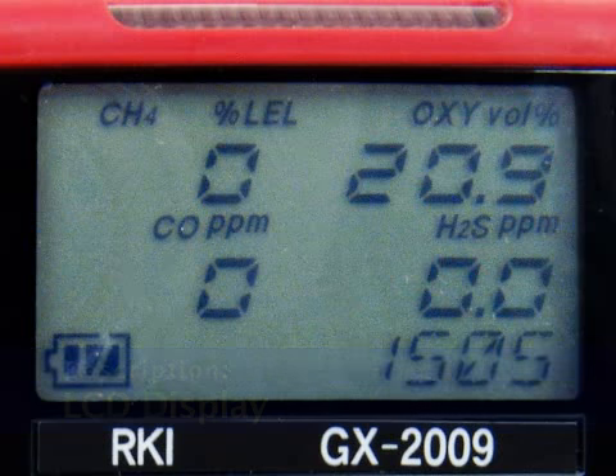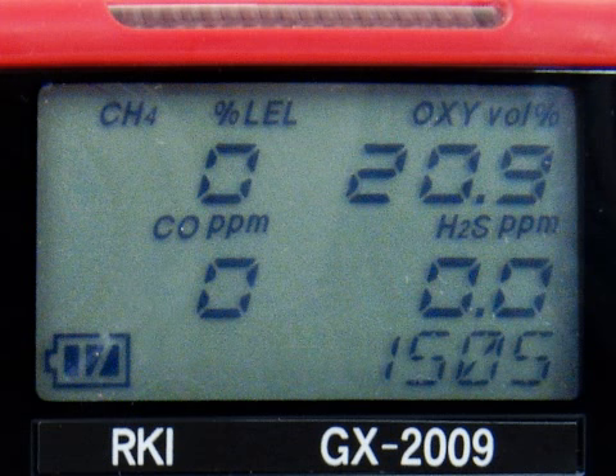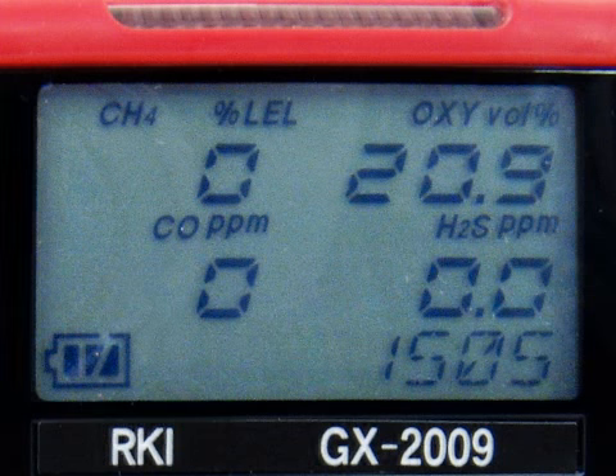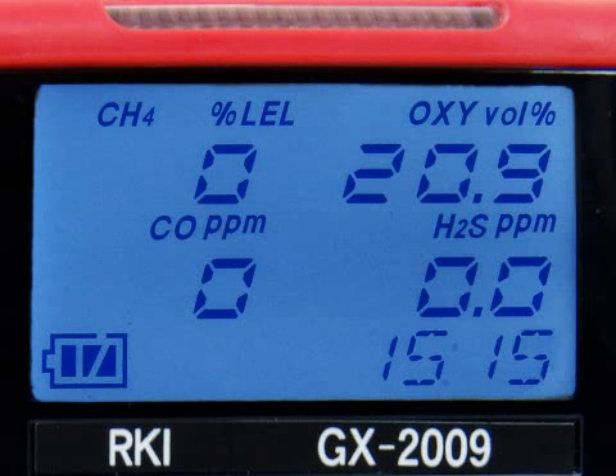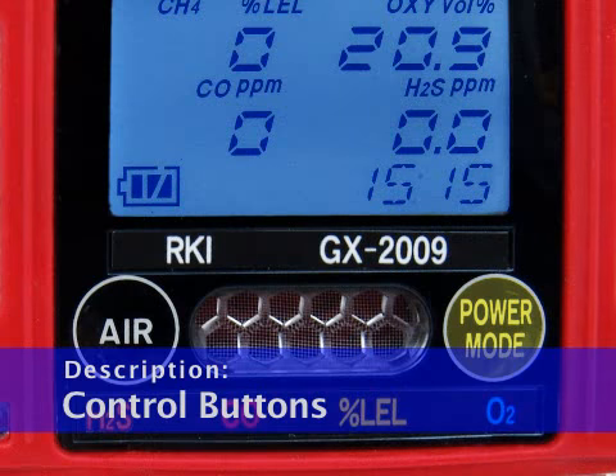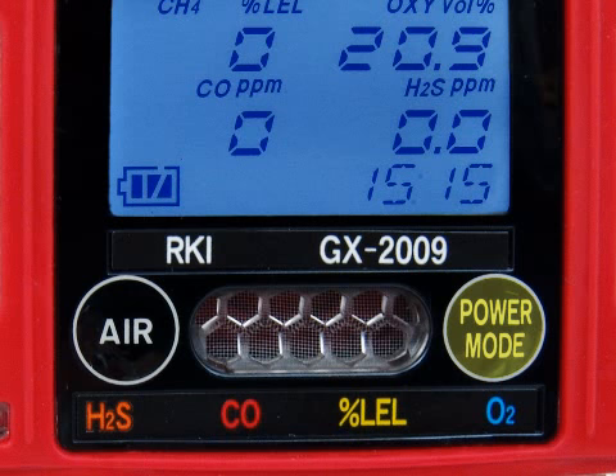The GX-2009's liquid crystal display during normal operating mode will show the current gas readings for all gas channels, the current time, battery conditions, and any alarm indications. When either of the control buttons are pressed, the LCD backlight comes on for 30 seconds. Two glow-in-the-dark control buttons are located below the display on either side of the front buzzer opening.